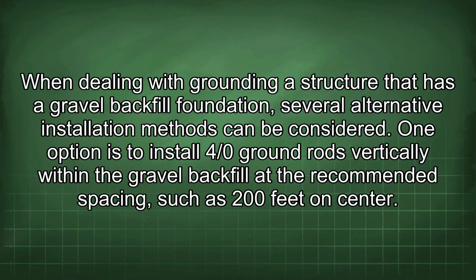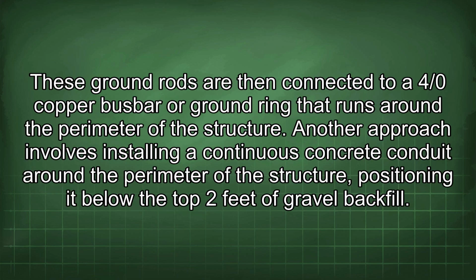When dealing with grounding a structure that has a gravel backfill foundation, several alternative installation methods can be considered. One option is to install 4/0 ground rods vertically within the gravel backfill at the recommended spacing, such as 200 feet on center. These ground rods are then connected to a 4/0 copper busbar or ground ring that runs around the perimeter of the structure.